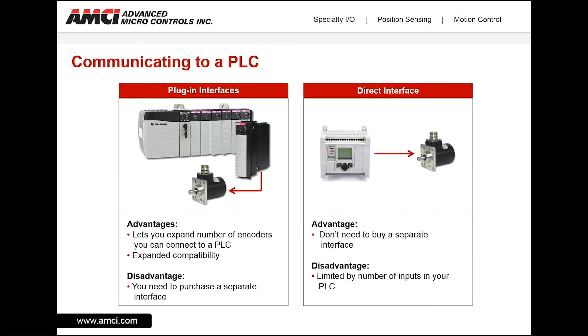Now that we have our sensors, how do we get that information into our controller? We'll assume that controller is a PLC, as it's the most common form of control in industrial automation. The first method is to use a plug-in interface. This allows you to expand the number of encoders you can connect to a PLC. If you have a sensor such as a resolver or an SSI encoder, you need to add a plug-in module, which expands the compatibility and types of sensors you can use. The main disadvantage is that you need to purchase a separate interface for each type of sensor.